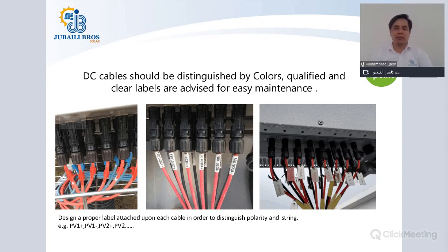So you are highly advised to do proper tagging under execution, and you are recommended to do temporary tagging. And once the installation phase is completed, you can go ahead and do permanent tagging of the PV cables. Normally, such naming can be done as PV1 plus, which refers to string 1 positive, and PV1 negative, which refers to the negative side of your string 1. A similar fashion of tagging you can follow for the different string markings.